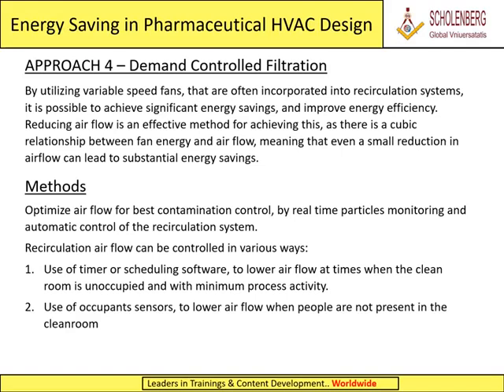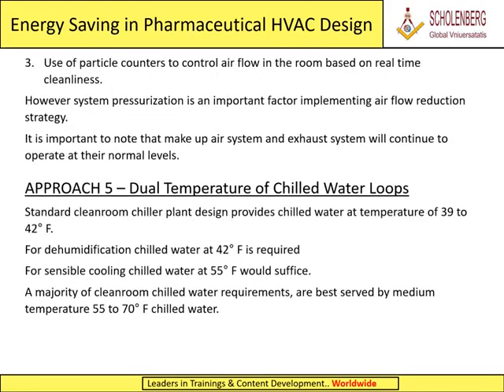Methods. Optimize airflow for best contamination control, by real-time particle monitoring and automatic control of the recirculation system. Recirculation airflow can be controlled in various ways. 1. Use of timer or scheduling software, to lower airflow at times when the clean room is unoccupied and with minimum process activity. 2. Use of occupant sensors, to lower airflow when people are not present in the clean room. 3. Use of particle counters to control airflow in the room based on real-time cleanliness.